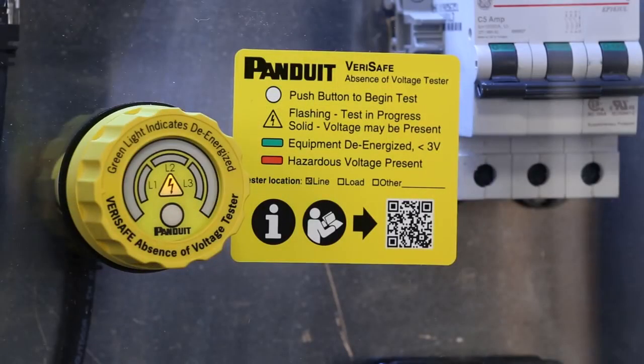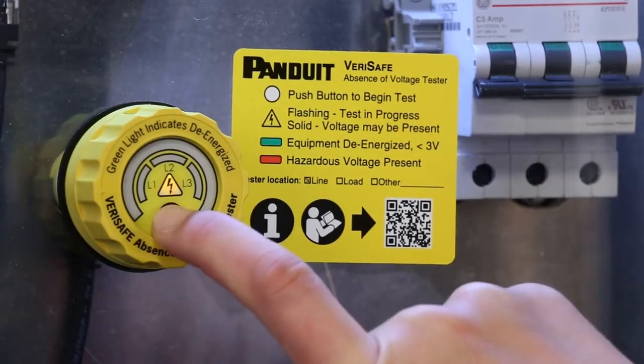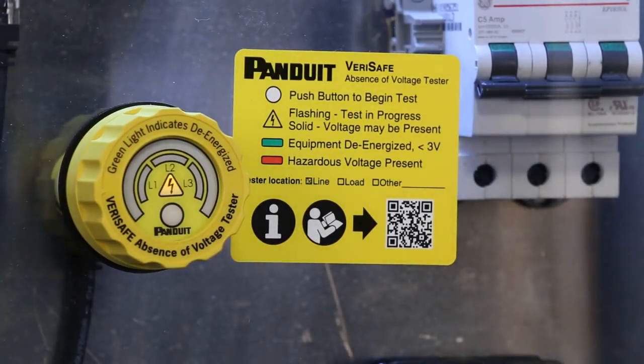But what if you get a yellow caution light? Let's demonstrate this condition. We will press the button to activate the test. The device returns the yellow caution light, indicating that there was a problem with the test. This could be from residual voltage in the system or a disconnected sensor lead.